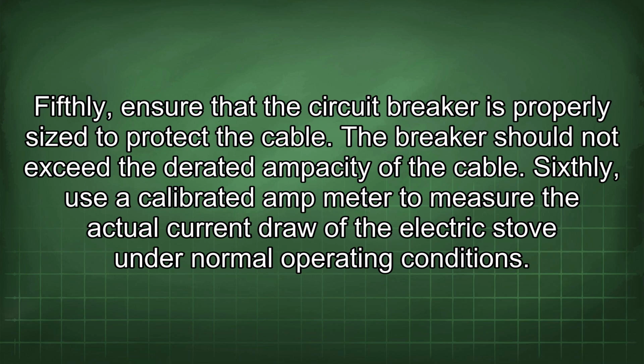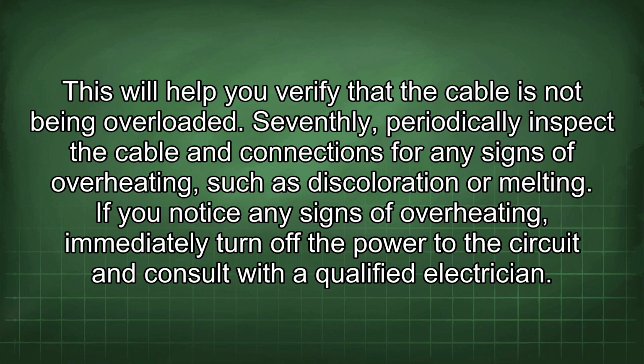Fifthly, ensure that the circuit breaker is properly sized to protect the cable. The breaker should not exceed the derated ampacity of the cable. Sixthly, use a calibrated amp meter to measure the actual current draw of the electric stove under normal operating conditions. This will help you verify that the cable is not being overloaded.